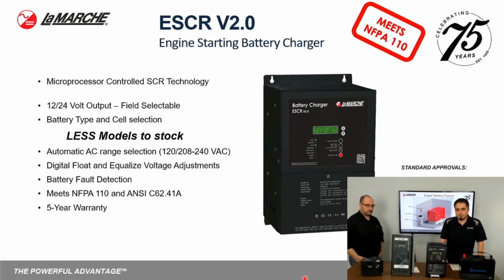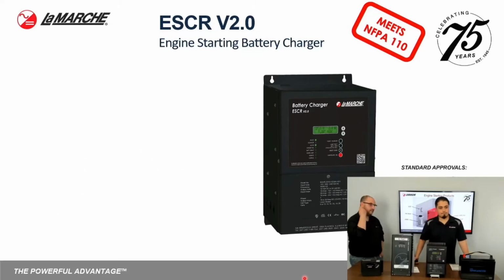It's still a microprocessor controlled SCR technology, and it has a 12 or 24 volt output selection which is field selectable, so you can do it through the menu structure here. There's no need for any dip switches or mechanical changes, so ultimately hopefully you have fewer models to stock out in the field. You also have automatic AC range selection with our wide range PFC, digital float and equalize adjustments, and battery fault detection. You're still meeting NFPA 110 and ANSI requirements as far as surge, all within a 5-year warranty, and again a UL 1236 package.